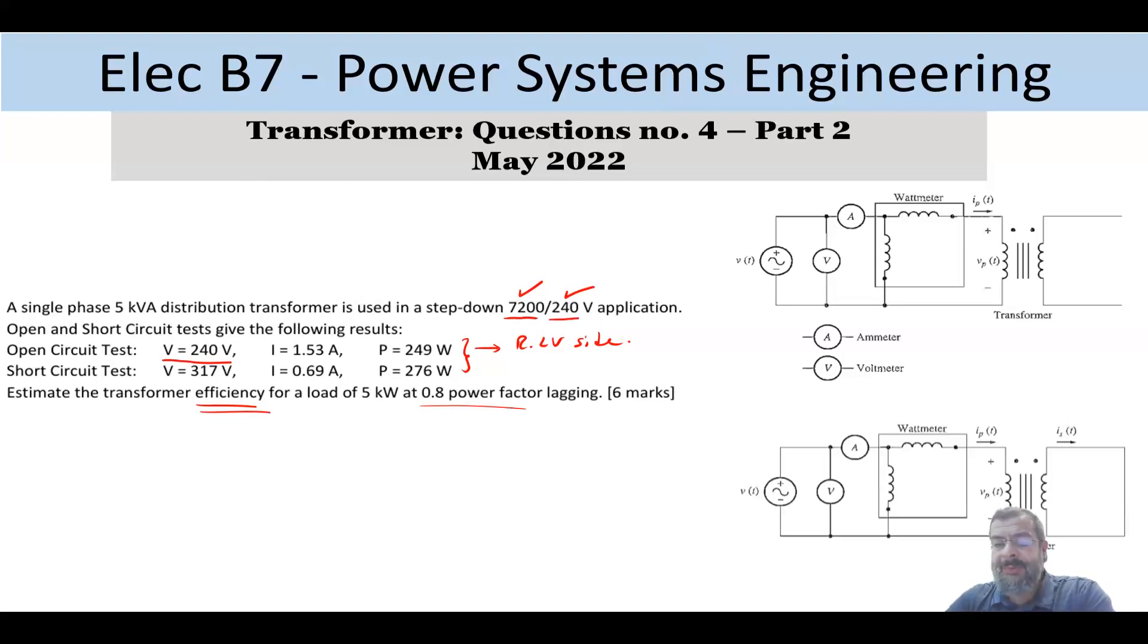Now in the short circuit test, which is this circuit here, the short circuit one side, and you apply the rated current. So you increase the voltage a little bit until you apply the rated current. In short circuit, we don't apply the rated voltage and rated current at the same time. So the voltage would be between 2 to 6% of the rated voltage. And usually, we do that from the high voltage side. So it's opposite.